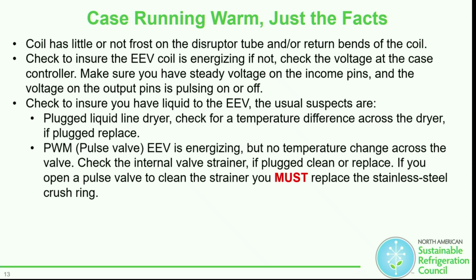Pulse valve: EEV is energizing, but no temperature change across the valve. Check the internal valve strainer. If plugged, clean or replace. If you open up a pulse valve to clean out the strainer, you must replace the stainless steel crush ring. Some are stainless steel. Some manufacturers use a rubber ring. If you are going to open that up, make sure that you have replacements on your truck. If you don't, come crying to me, I don't know what to do, it won't stop leaking. Now you're going to have to isolate the case for the night.